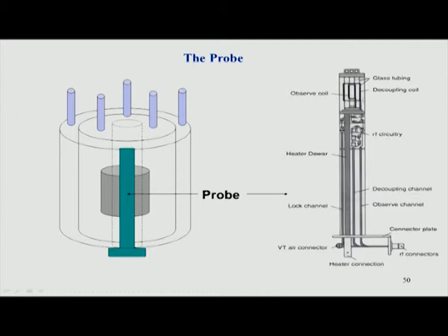With the sample sitting in the middle, the RF coil transmits the RF radiation to the sample, and also receives the signal from the sample. This signal passes through different capacitors and resistors, is then digitized, and is taken into the next part of the spectrometer.